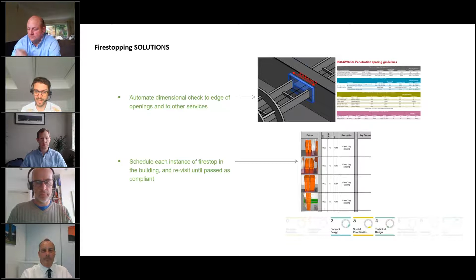Then through construction and into operation, this itemized list of firestops — which should be compliant and aligned with manufacturer's test data — gives us a mechanism to better control subcontractor installations. That's really important because there are typically three different subcontractors who influence where the partition goes, how big the builder's work opening is, how the services are spaced, and how the firestop is installed.